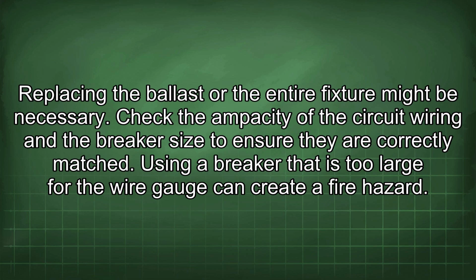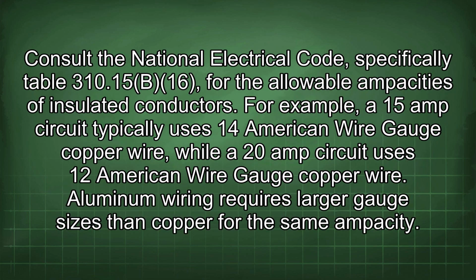Check the ampacity of the circuit wiring and the breaker size to ensure they are correctly matched. Using a breaker that is too large for the wire gauge can create a fire hazard. Consult the National Electrical Code, specifically Table 310.15(B)(16), for the allowable ampacities of insulated conductors. For example, a 15-amp circuit typically uses 14 American wire gauge copper wire, while a 20-amp circuit uses 12 American wire gauge copper wire.